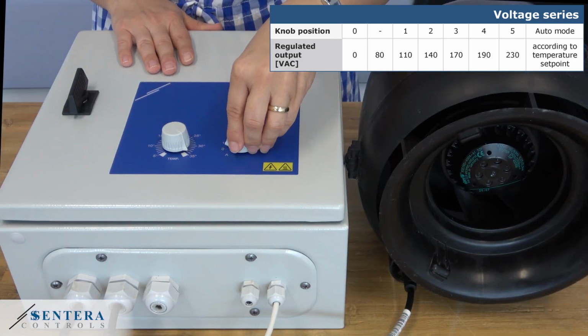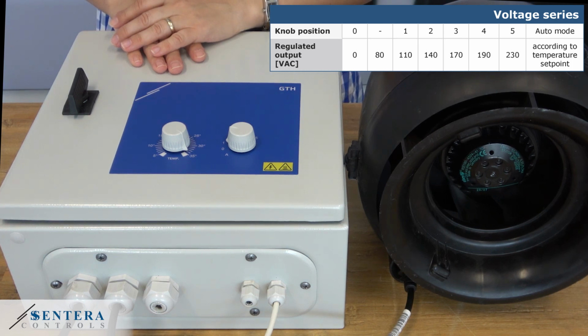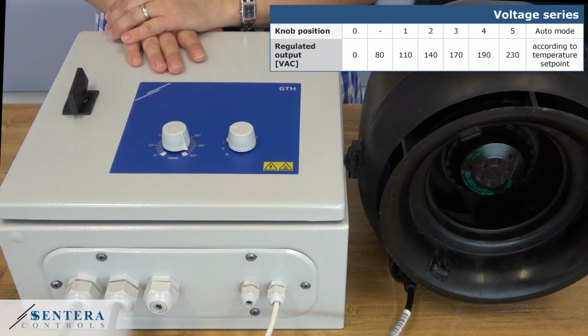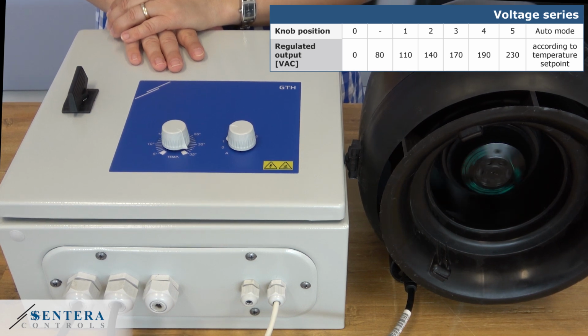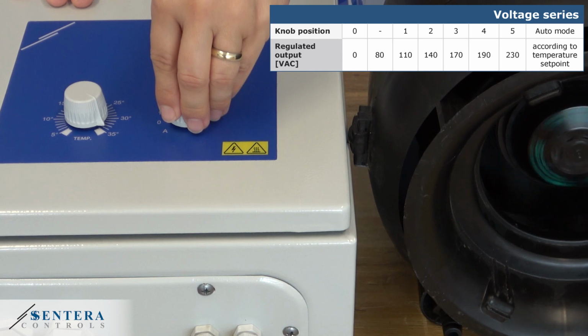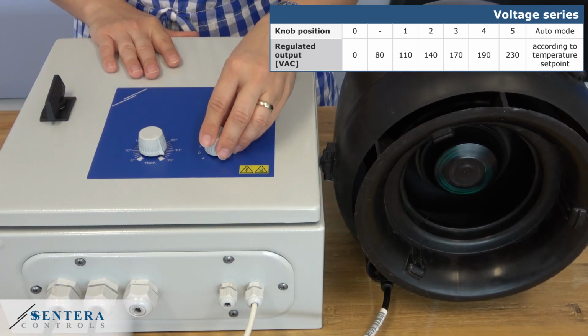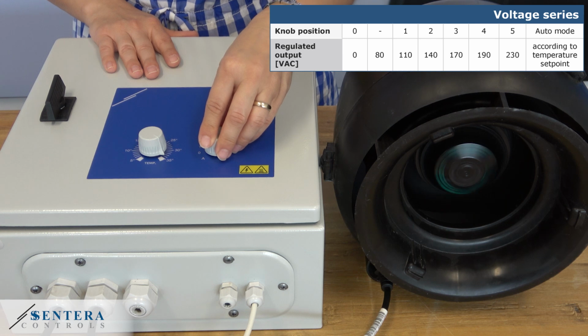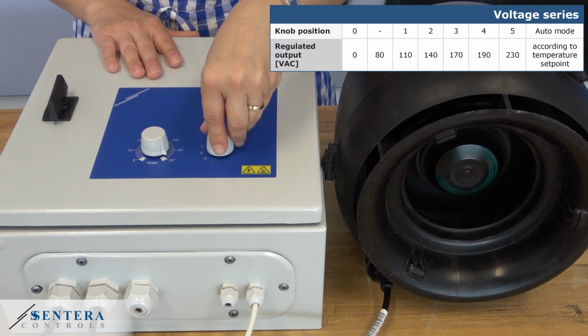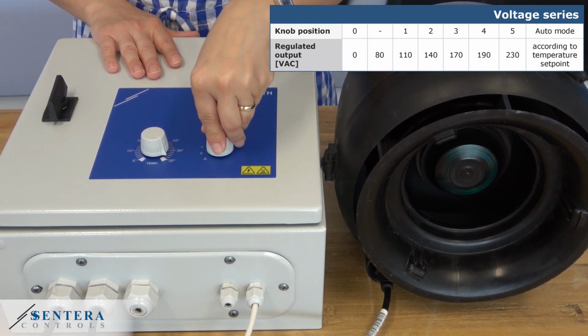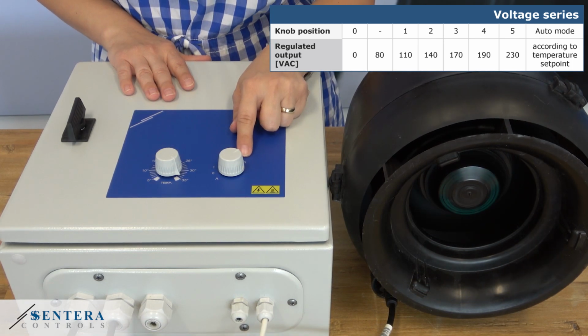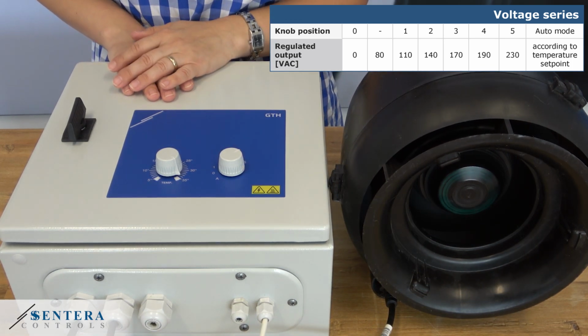Now I will operate it manually. Step 1. The output voltage is 110 VAC. I will increase it and it goes to 140. When step 5 is activated, the motor is running using the supply voltage, which is 230 VAC. This is how the controller is operated as a standalone device.